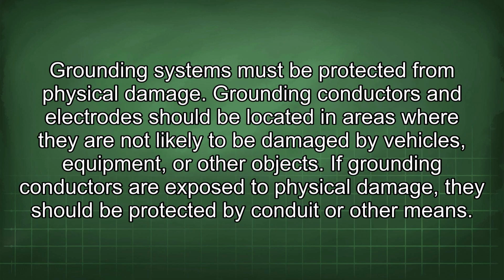Grounding systems must be protected from physical damage. Grounding conductors and electrodes should be located in areas where they are not likely to be damaged by vehicles, equipment, or other objects. If grounding conductors are exposed to physical damage, they should be protected by conduit or other means.